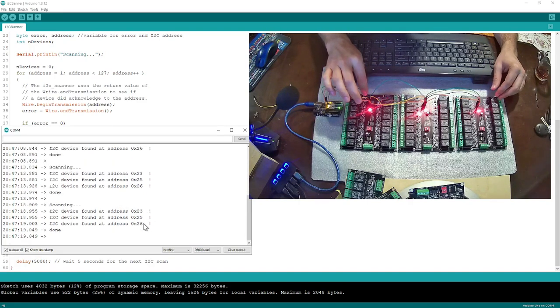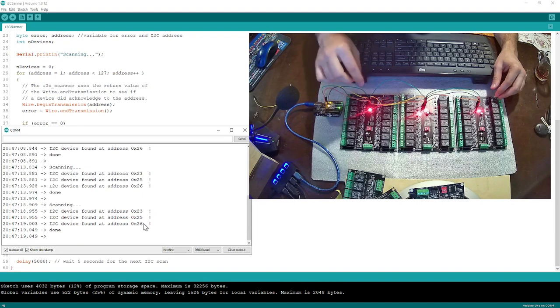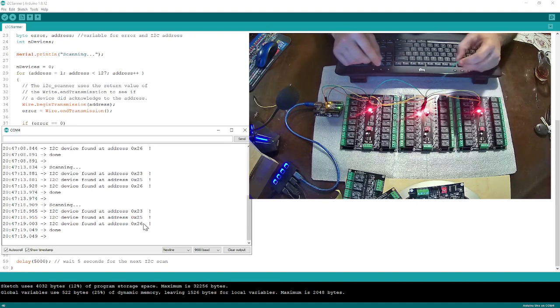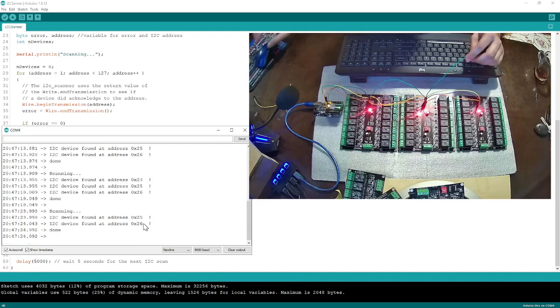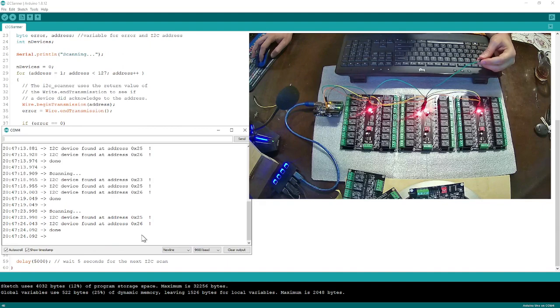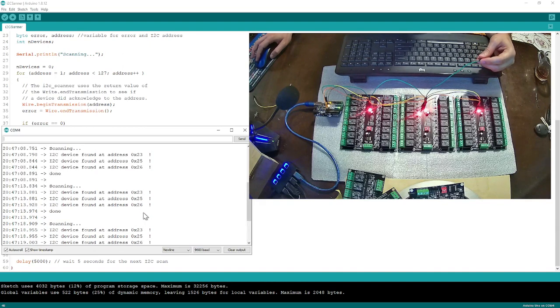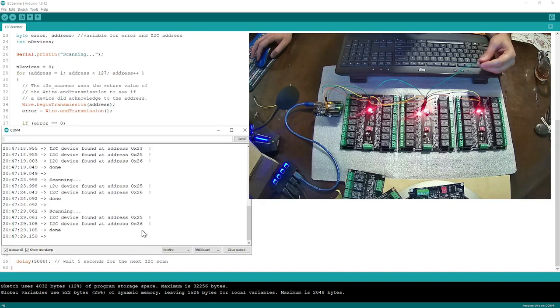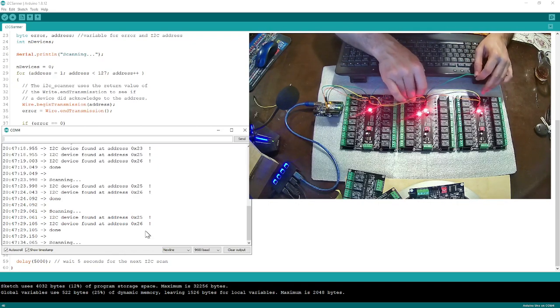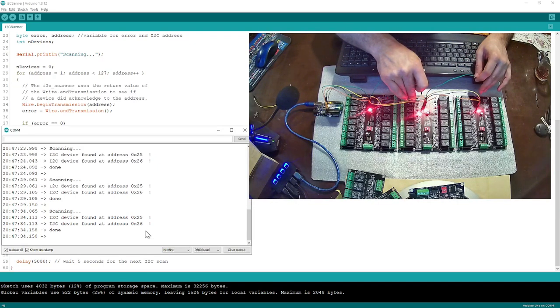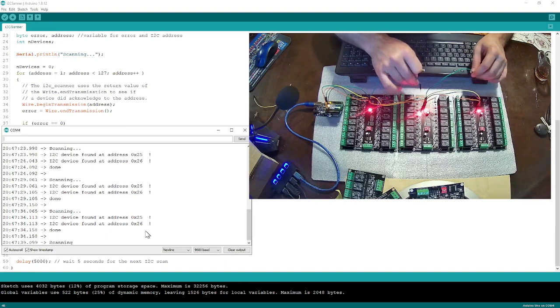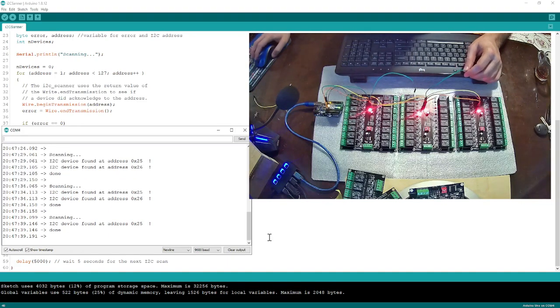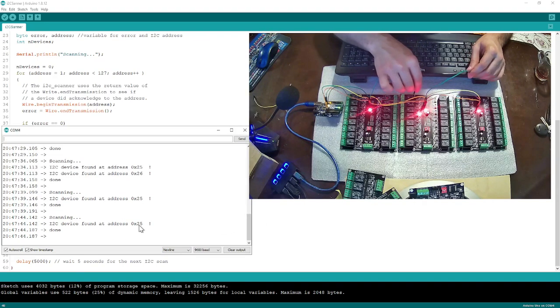For example, I'm going to unplug this one. When I unplug it, I lost one of them — which one did I lose? Looks like 23. So this board is address 23. Now if I disconnect this one, the screen is going to refresh. Now I have only 25, which means this one is 25.